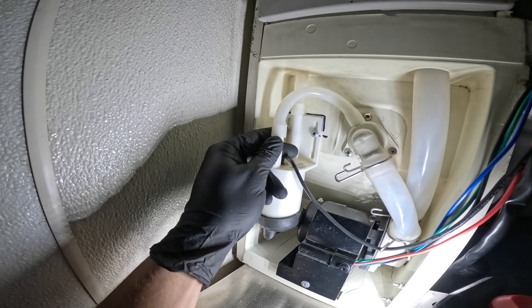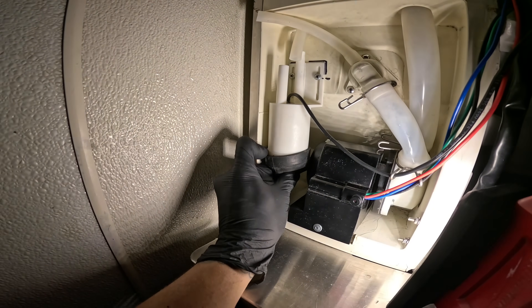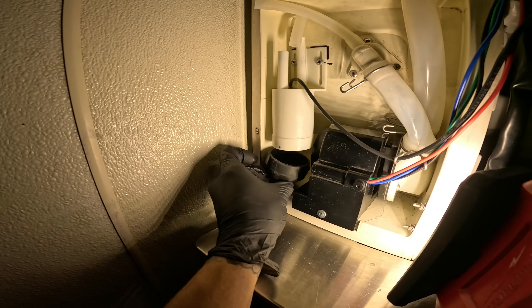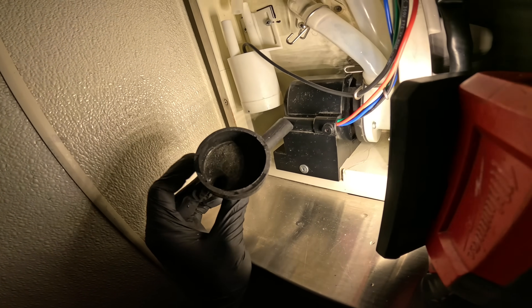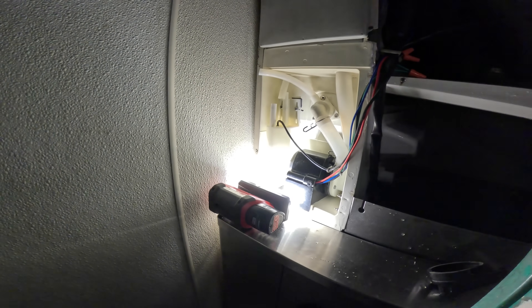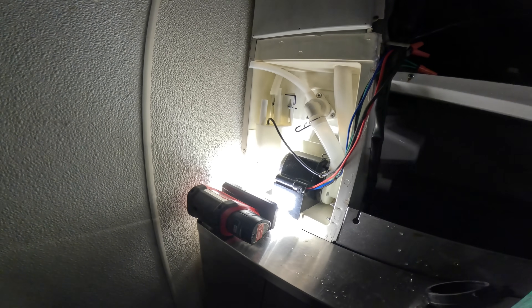To make things a little easier, take out this piece and this piece right here — careful not to mess that up. It connects to that piece in the back — just a little cup. Looks like it got a bit more dirt already since the last visit — this thing is getting dirty, it's time for a cleaning. It's moving now — it was stuck up before. I'll show you some literature from the manufacturer about the code we had — the three-beep alarm — it gives you some tips.